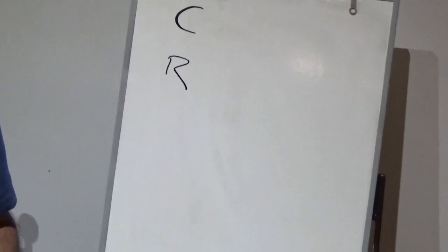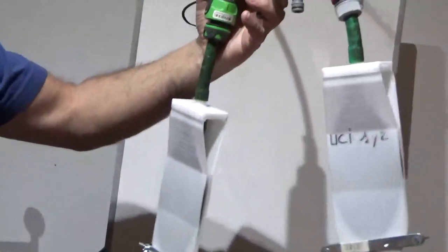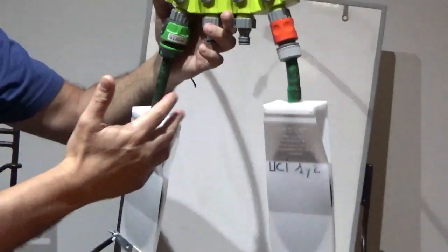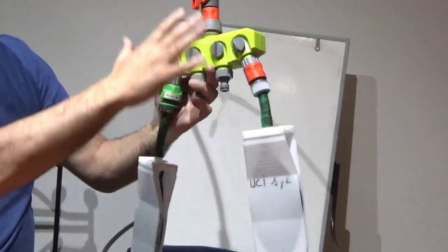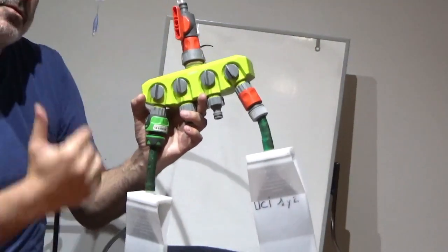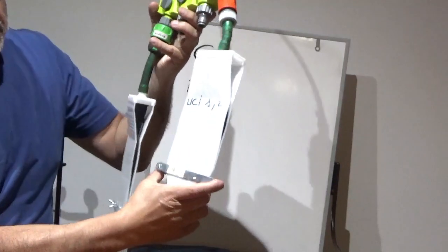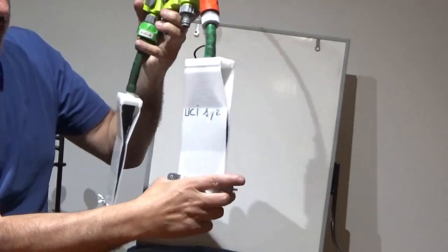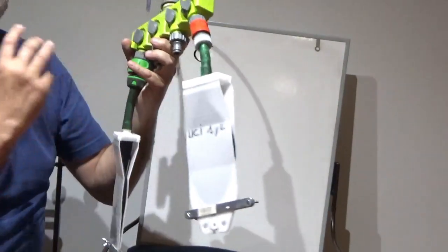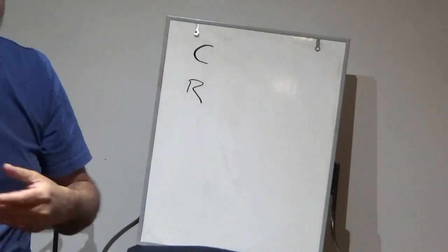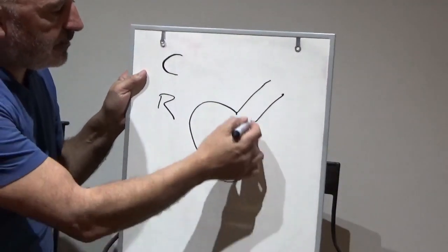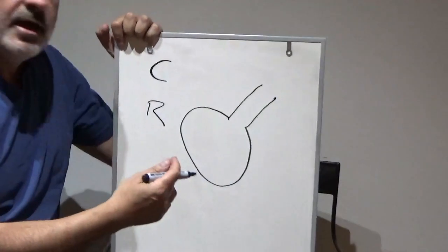the ventilator, I have here our simulator, and as you can see we have two test lungs simulating two lungs, and we have here the bulb. With this bulb we can simulate, increase or decrease the resistance. With these devices we can compress the lungs in order to decrease the compliance. This is very interesting because this is absolutely the same that we have when we try to study the respiratory system.